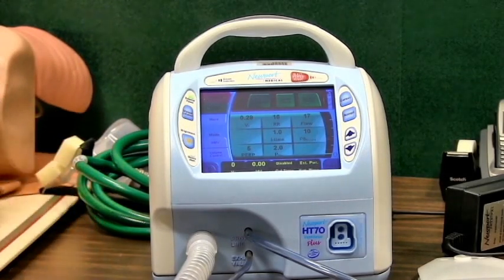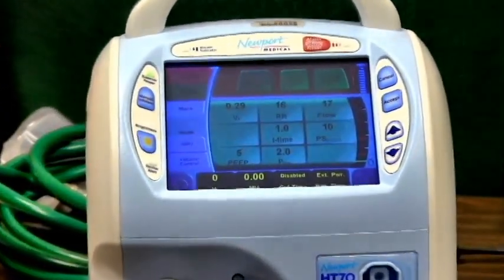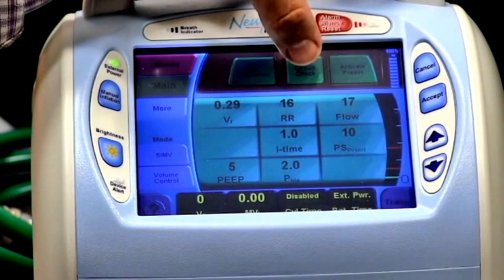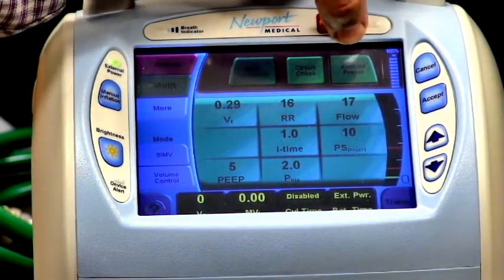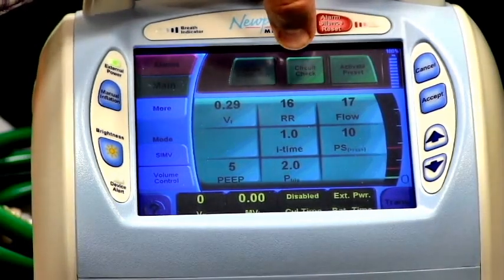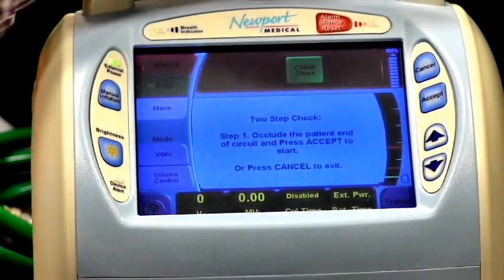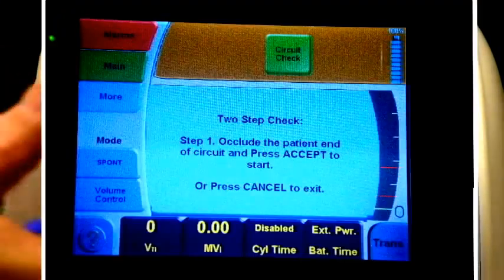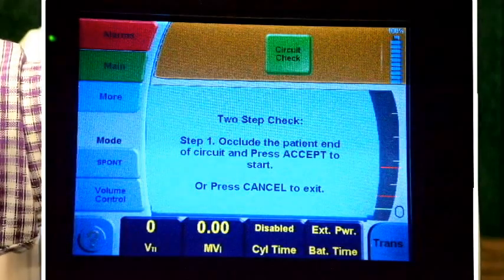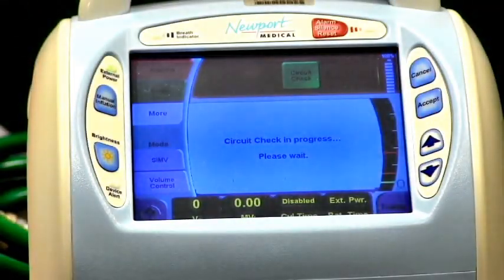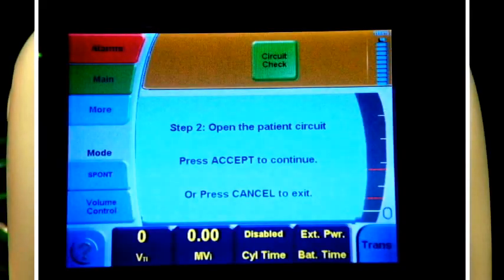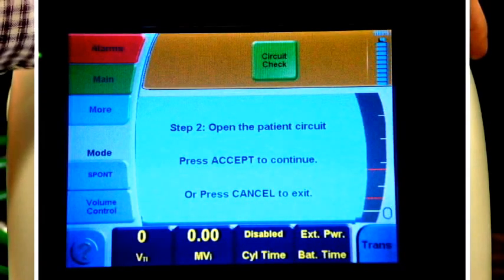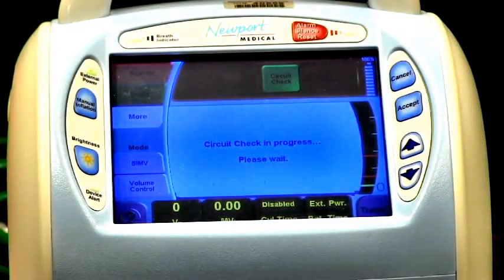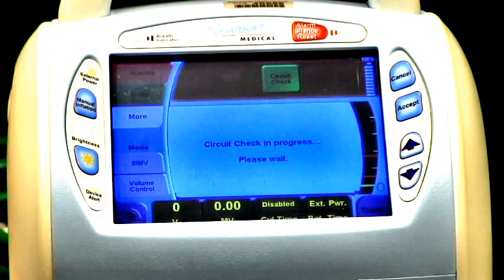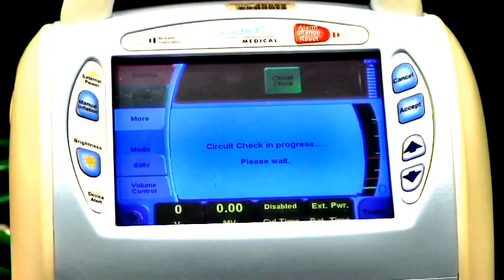Going through our circuit check here, let me zoom in just so you can see it as it goes through. As I start the circuit check, up here you have 3 buttons: start ventilation, circuit check, and activate preset. Circuit check is what we're interested in. We're going to hit circuit check. It's going to tell us to occlude the patient end of the circuit with our finger. So we put your thumb over the end of it here and press accept. Once I hit accept, it's going to push air through against my thumb. Make sure that it is completely occluded, otherwise it will fail the test. Once you're done, it will say open the patient circuit. So you take your thumb off the circuit, press accept to continue, and now it's going to go through its piston check. It's going to run through the pistons and blow air through the circuit to check its internal parameters and the max flow rates and things like that.